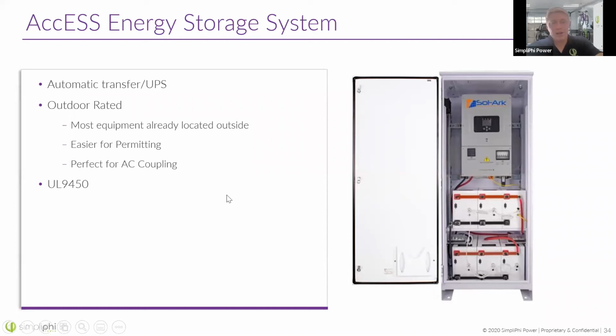This entire enclosure and everything inside of it is 9540 rated, and even multiples of them in parallel are 9540 certified. So this is, I would say, a very popular solution for AC coupling, as all of your AC coupling equipment is already outside. Adding this cabinet in line, as we saw earlier, is easy because you don't have to bring any wiring inside.